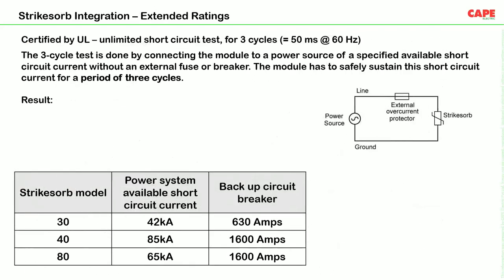Strikesorb series SPDs are again certified by UL for unlimited short circuit tests for 3 cycles. That means each SPD has been given a short circuit current for 50 milliseconds at 60 Hertz frequency. Below are the power system available short circuit test currents for the different models. Strikesorb 30 was tested with 42 kiloamperes short circuit current. Strikesorb 40 was tested with 85 kiloamperes, and Strikesorb 80 was tested with 65 kiloamperes short circuit current.